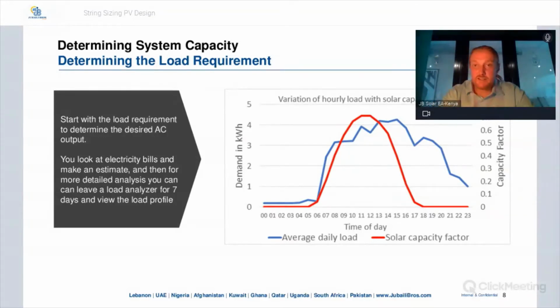We know that the peak hours of the sunlight happen in the noontime. And then, of course, in the early morning and evening, there's not much sun. So it's important that you get this 24-hour load profile so you can calculate accurately how much of their load can be carried by the solar energy. And this also gives you a chance to do some optimization on their load, because you can ask them to try to move the evening loads to the peak hours of the sunlight, and that would maximize their solar load.